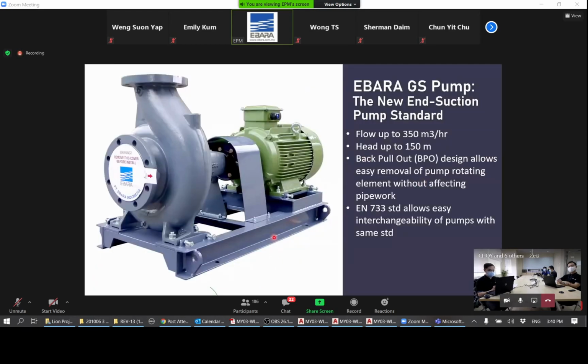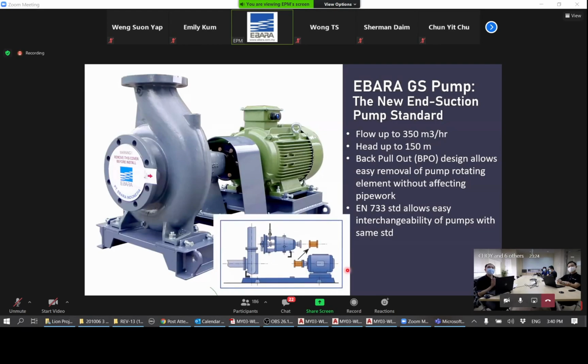So the new Ebara GS series has a very big flow range of up to 350 meter cube an hour, and even heads up to 150 meters, and has a very good, what we call a BPO, back pull-out design, which allows easier removal of the pump rotating parts here without affecting the pipe work. So in cases where you need to take out the pump for maintenance or to inspect the pump, you can just remove the pump body without affecting the casing, so that the casing and the pipe do not need to be removed. So it's a very good design.